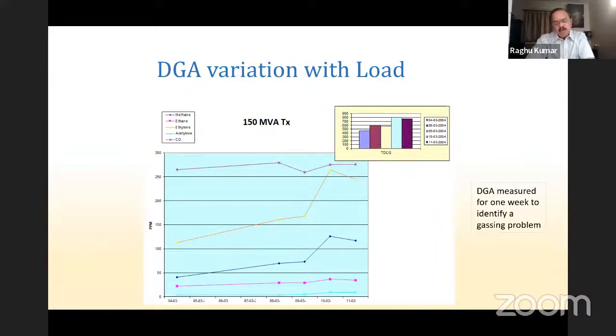Later on, over a period of time, it was assessed and found that the transformer can be safely operated at 60 MVA. We kept the load at 60 MVA, and the transformer was operated until an expert arrived from the manufacturer. Then an internal inspection was carried out.